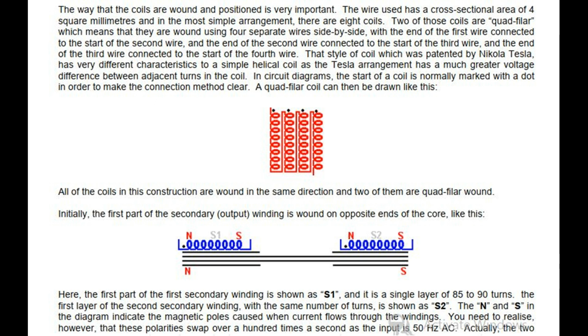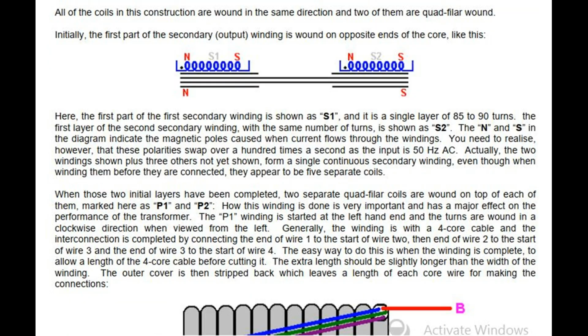Here, the first part of the first secondary winding is shown as S1, and it is a single layer of 85 to 90 turns. The first layer of the second secondary winding, with the same number of turns, is shown as S2. The N and S in the diagram indicate the magnetic poles caused when current flows through the windings. You need to realize, however, that these polarities swap over 100 times a second as the input is 50 Hz alternating current. Actually, the 2 windings shown plus 3 others not yet shown, form a single continuous secondary winding, even though when winding them before they are connected, they appear to be 5 separate coils.